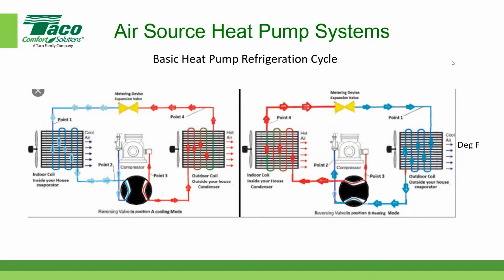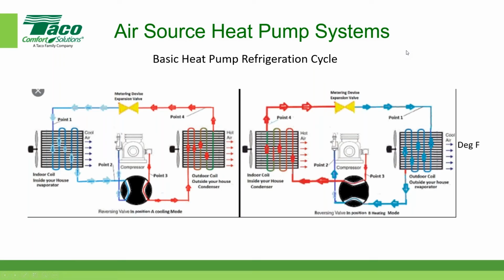All right. Let's see. Do I have another valve diagram? Is this valve also used for defrost? Yes. Okay. So some manufacturers will use the reversing valve to cause the outdoor unit, remember, this is the outdoor unit over here, and the outdoor unit, when it's in the heating mode, is actually extracting heat from a very low temperature. So the air is going across this coil, but it can freeze up. In which case, they reverse the reversing valve and put hot refrigerant in the outdoor coil to melt the ice or defrost it. Some manufacturers use that methodology. Others use an electric resistance heater to heat the outdoor coil.